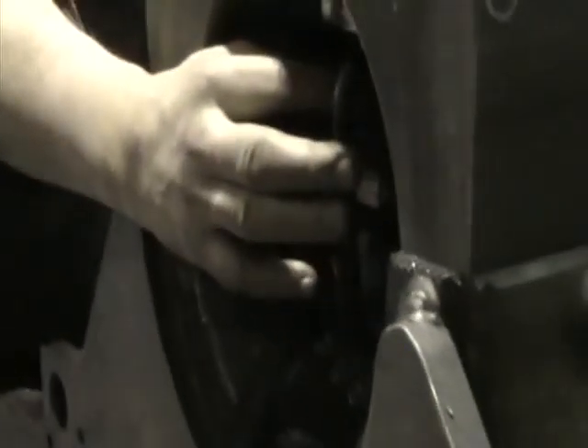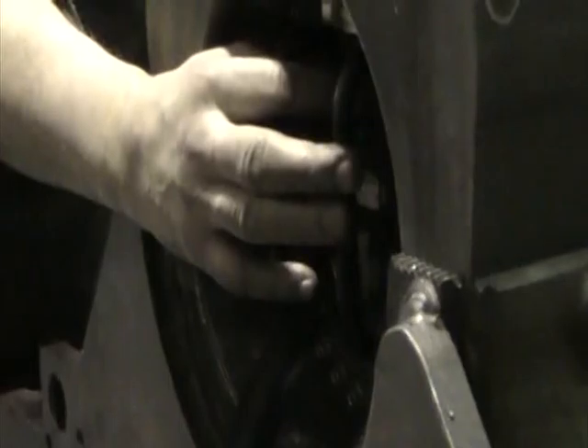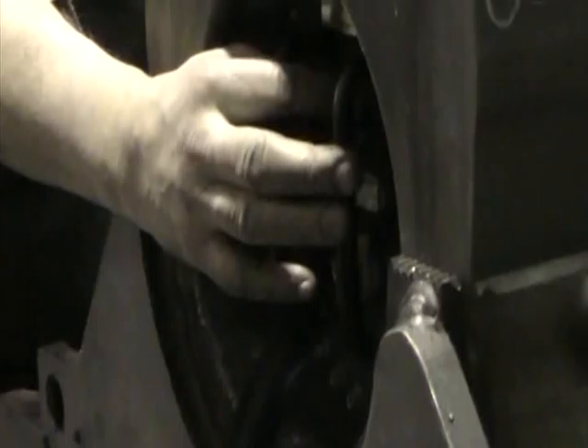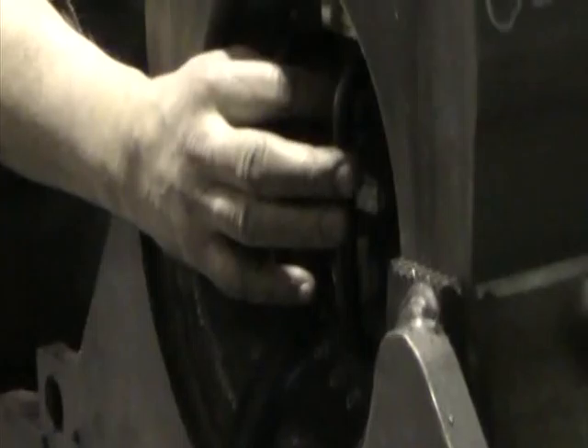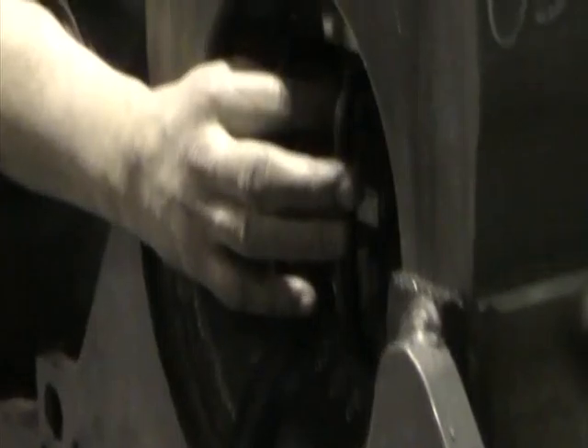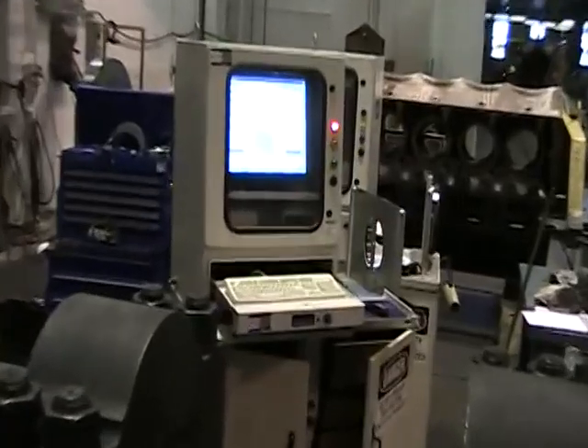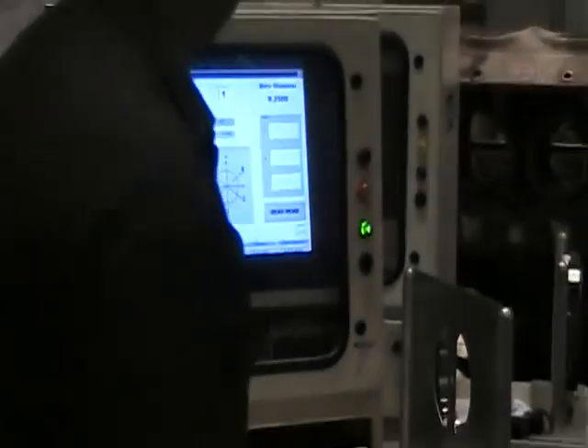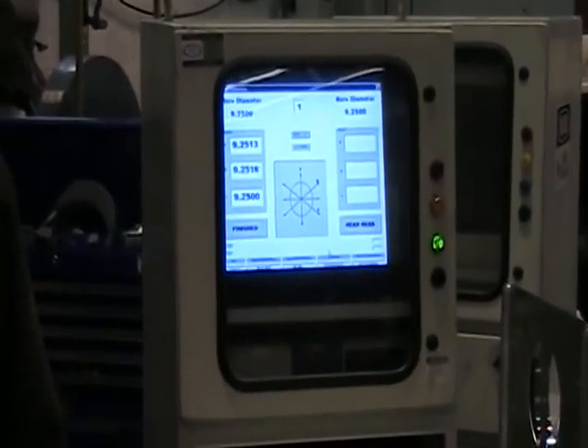To commence a reading, push the button on the back of the probe. Push the button with your index finger while keeping a grip on the probe handles. This will ensure that the probe isn't jarred by the button push. Remove your hand and wait 3 seconds for the laser to take a reading. There is an audible tone and an indicating light that show a proper reading. Once you hear the beep, you are free to move to the next reading.